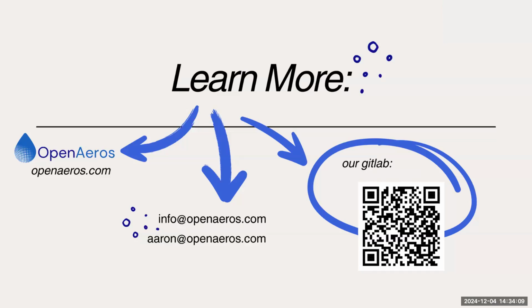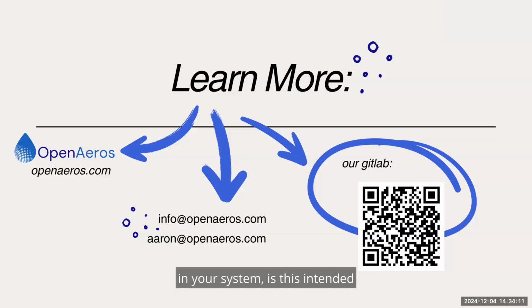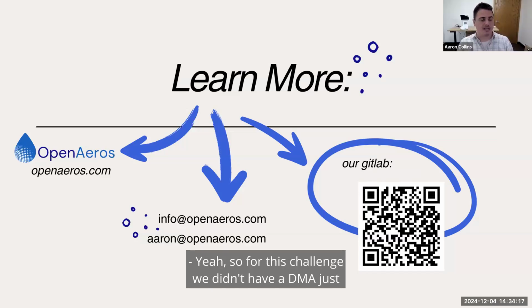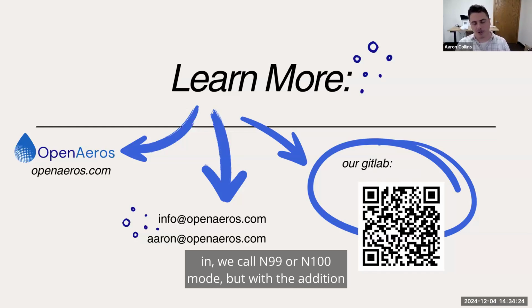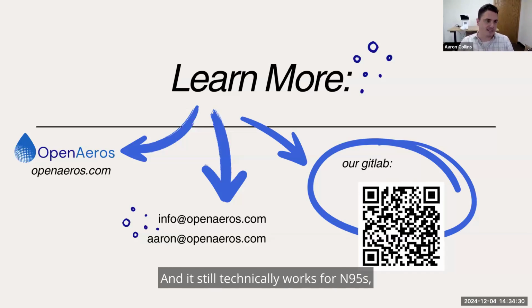Since there's no DMA involved in your system, is this intended to be used only with N100 masks? For this challenge, we didn't have a DMA because of the time scale. Right now it only works in what we call N99 or N100 mode. With the addition of an electrostatic classifier, it would be compatible with N95 as well. It still technically works for N95s, we're just less sensitive, because of filter leakage that can happen through the filter media itself.